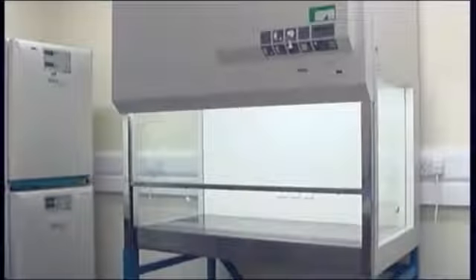Microbiological safety cabinets, also referred to as MSC2 cabinet or hood. Probably the most important piece of equipment for cell culture, since when operated correctly, it provides a clean working environment whilst protecting the operator. Operator and product protection is provided through a combination of airflow, negative pressure and HEPA filters. Cabinet exhaust may be ducted to atmosphere or recirculated through a second HEPA filter back into the laboratory.